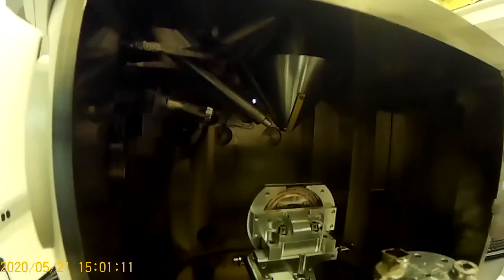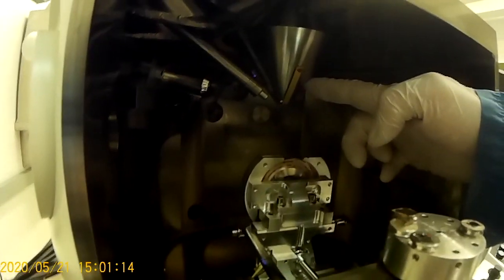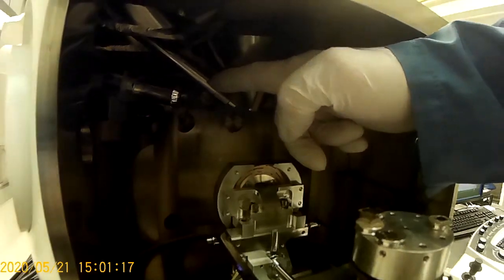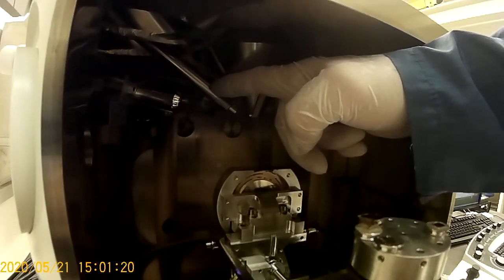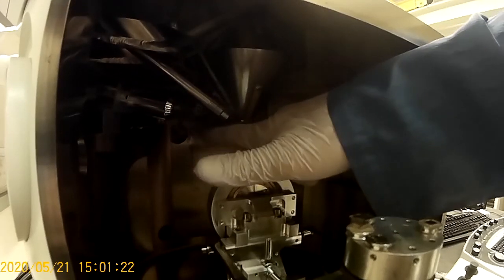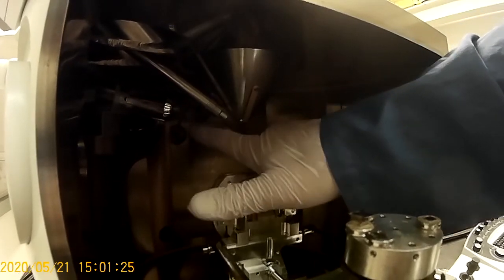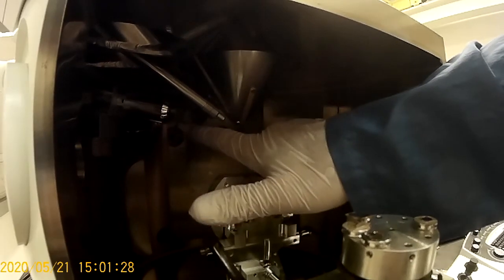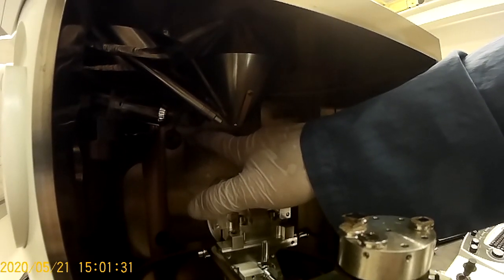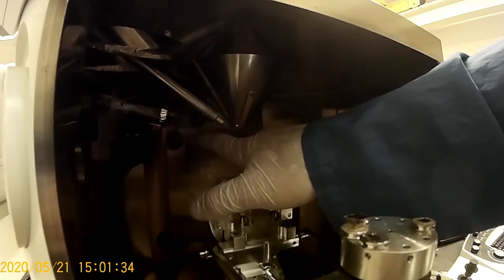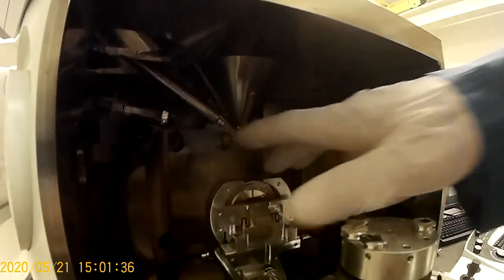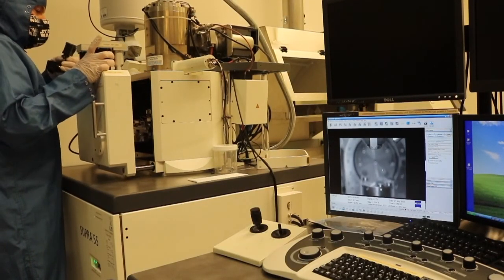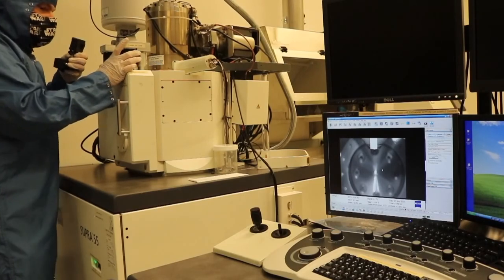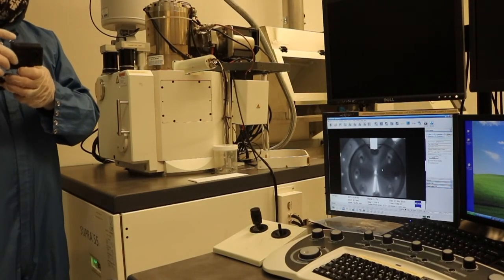Looking inside of the chamber, you can see the bottom of the final lens is here. The front of the X-ray analysis detector is here, EDS, energy dispersive spectroscopy. Behind that is the secondary electron detector, of the Everhart Thornley type. That's the small cage that is here. There is a backscatter detector available. It is a Robinson backscatter detector, which is a scintillator type. And then there's a through-the-lens secondary electron detector, which is located here. You can very gently push the door shut. And then once the door is shut, you can pump the system down.